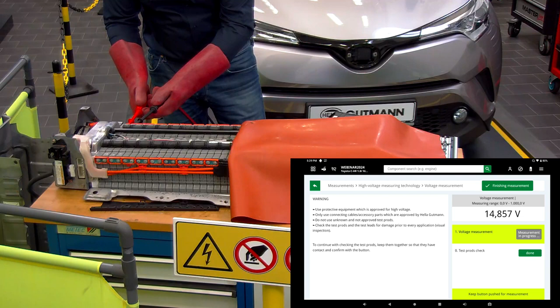I go to the first two contacts, and we have there 14.865 volts. Very good. But how many things are we now measuring, Pete? What do you think? We're measuring 2 modules. Exactly. This is very important. So we're going positive on one module to a negative. Then we go to the normal outside measurement, positive, negative. Remember, they are connected in a row. So if I go to the other side, to this side, and to this side, then we have 7 point whatever volts. Yeah, now I press. 7.46. Yeah, it's around that.